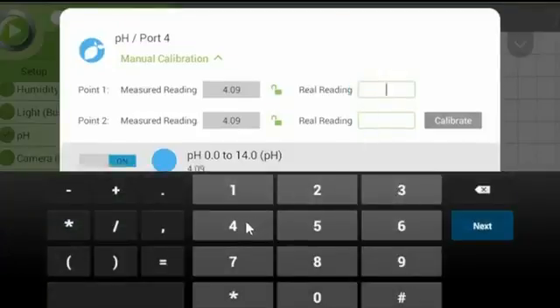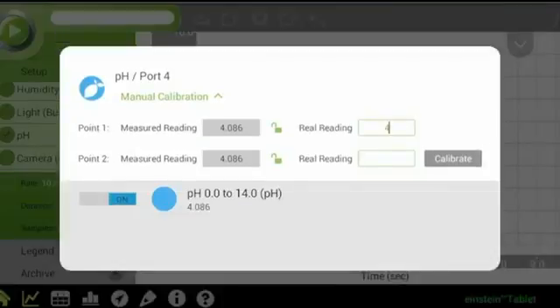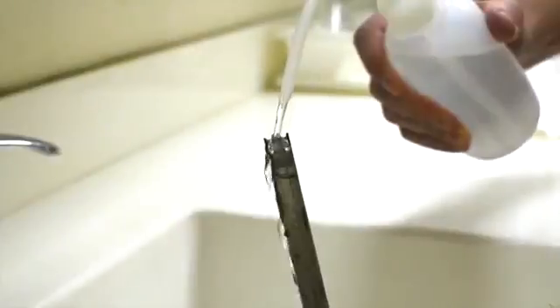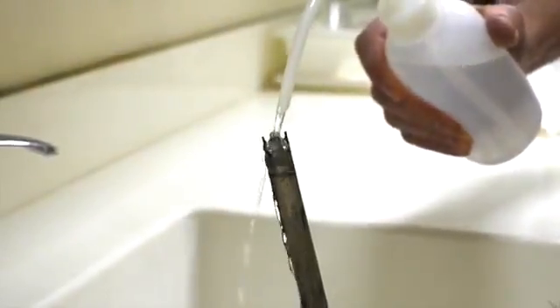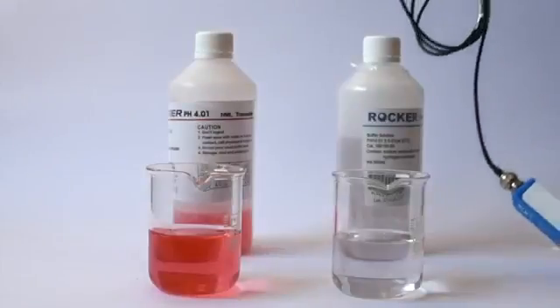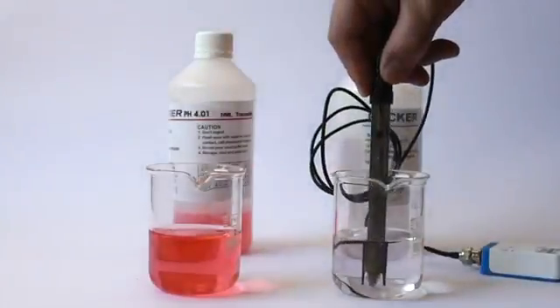Tap the real reading box, enter 4 in the real reading 1 box. Wait for the readings to stabilize. Tap the lock icon. Rinse the electrode with distilled water. Insert the pH electrode in a container of pH 10 buffer.